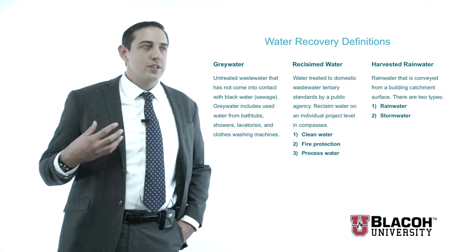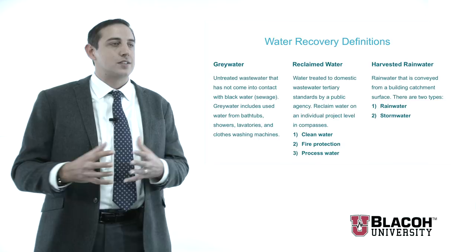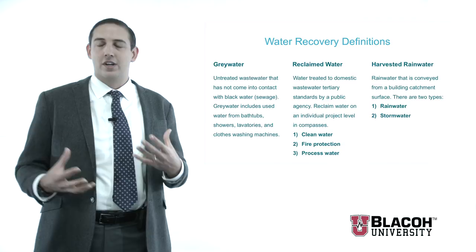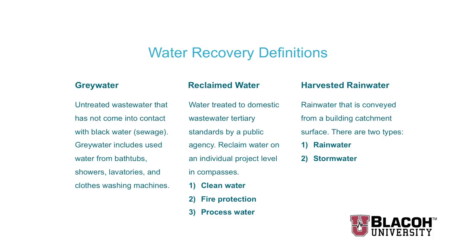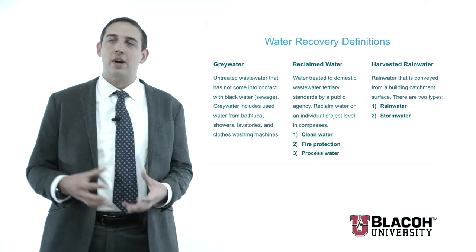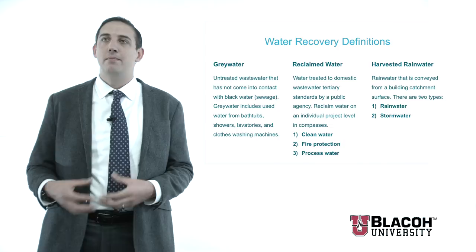I always like to open up with a brief understanding of what we're talking about. One of the things that comes up a lot when doing these types of systems is the nomenclature. We break it down into three distinct classifications. Most of you are familiar with gray water. Gray water is untreated wastewater that has not come in contact with black water or sewage. This is essentially any water from hand washing to dishwashers to laundry machines that has not been used in any kind of food preparation. Food preparation is classified as dark gray water.